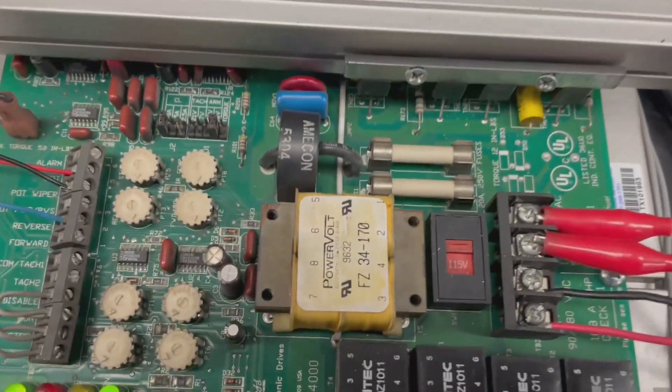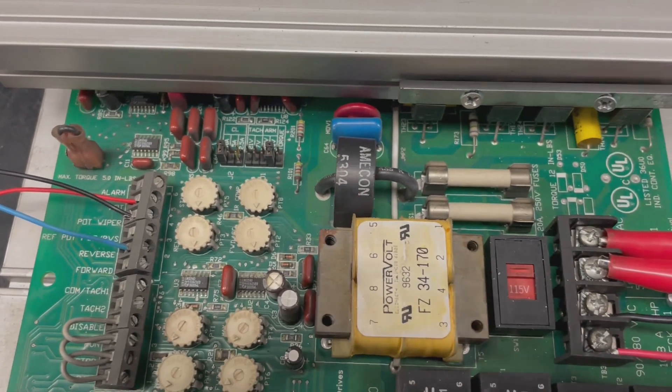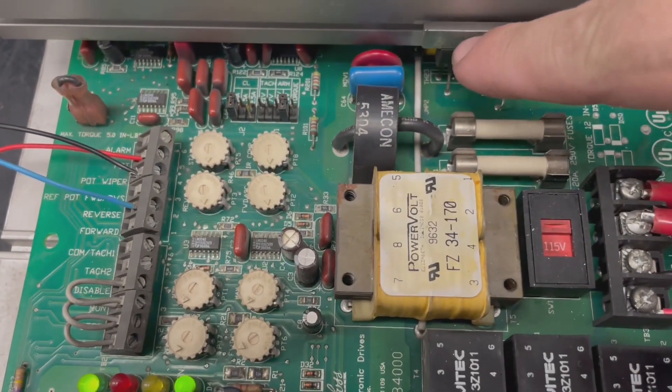We have resolved the issues with this drive which consisted of the thyristor controls here and also these transistors that control the output of this DC drive.